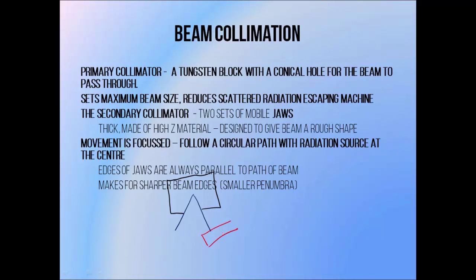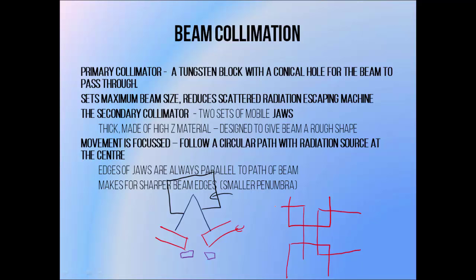Linear accelerators use three levels of beam collimation. The primary collimator is a thick tungsten block with a hole in it to let the beam out — it determines the maximum field size, and also helps stop scattered radiation from escaping the treatment head. Beneath this we have the secondary collimator, or jaws, which are four mobile rectangular radiation shields made of thick metal. They're moveable and allow us to make square and rectangular fields. A linear accelerator has two sets of jaws, one above the other, and these jaws can move independently so they can make any square or rectangular beam shape within the bounds of the maximum field size.